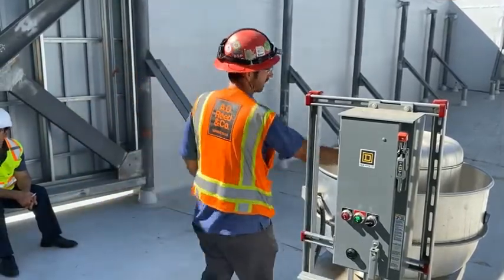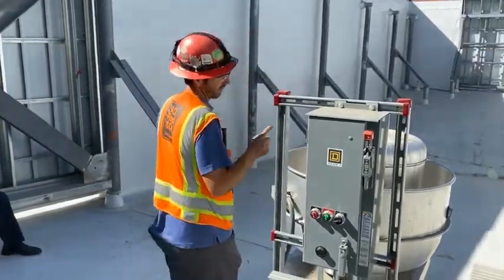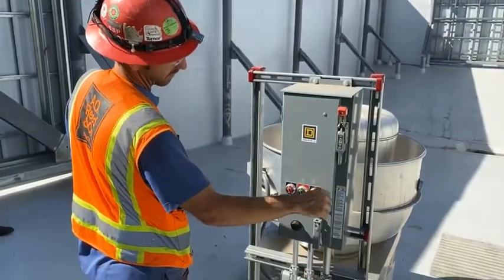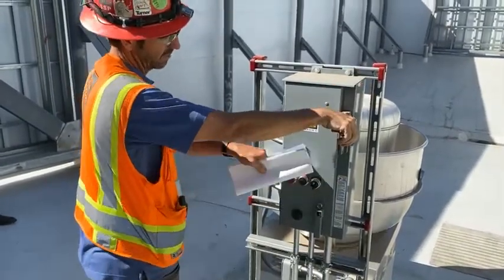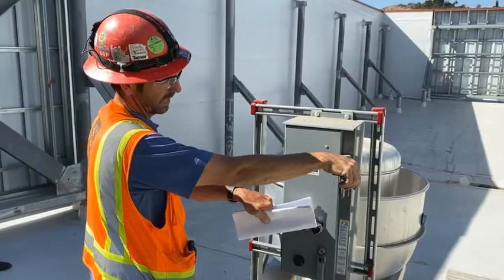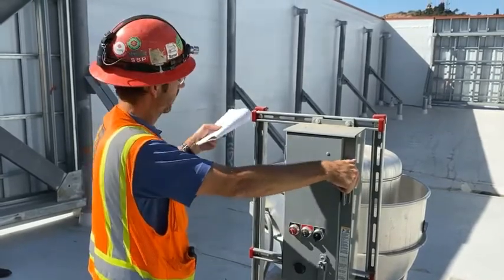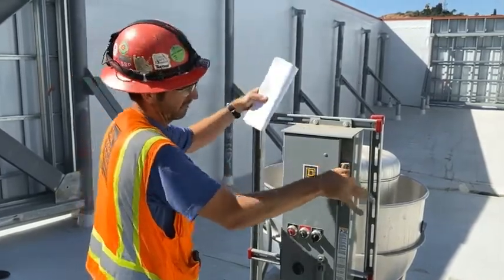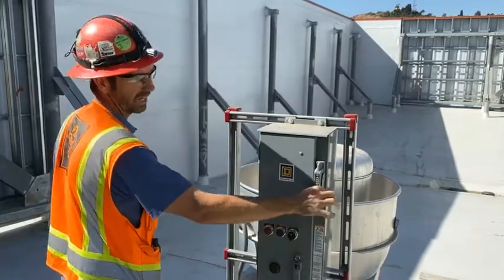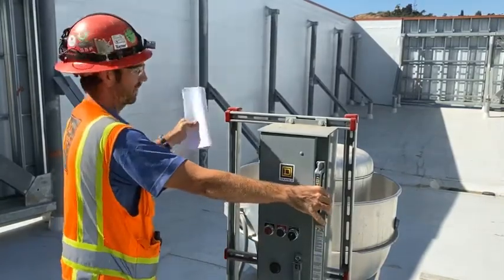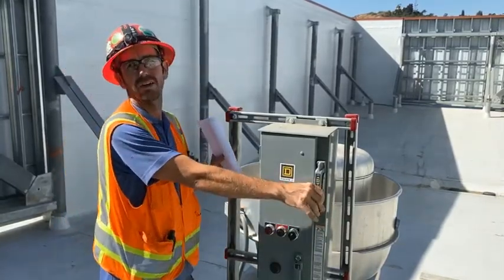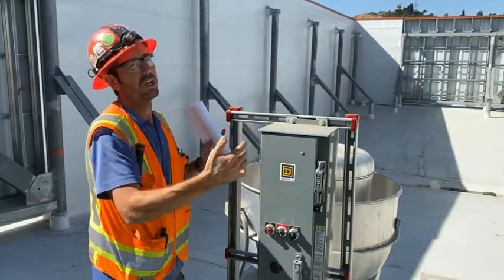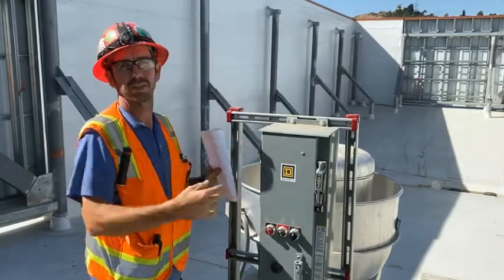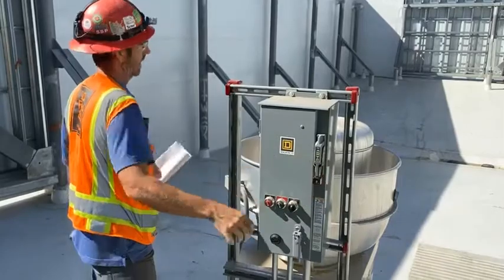These are belt-driven units. Now that we're going to be looking at this, we're going to turn it off. Again, that switch doesn't per se turn off power. If we're working and putting our fingers in the unit, we need to turn off the main disconnect. We'll put a lockout tagout here. Even if you're standing right next to it, lockout tagout. If you walk away and somebody comes over, they might turn it on. Anytime you're putting your fingers in, lockout tagout.